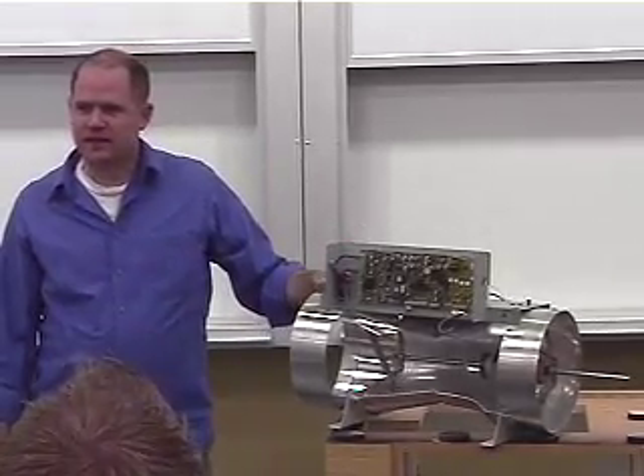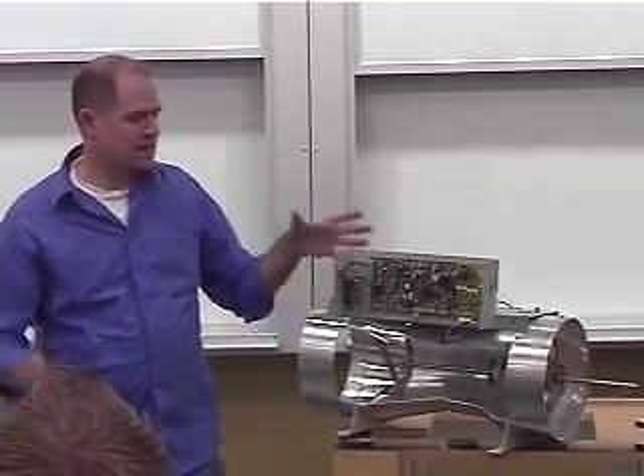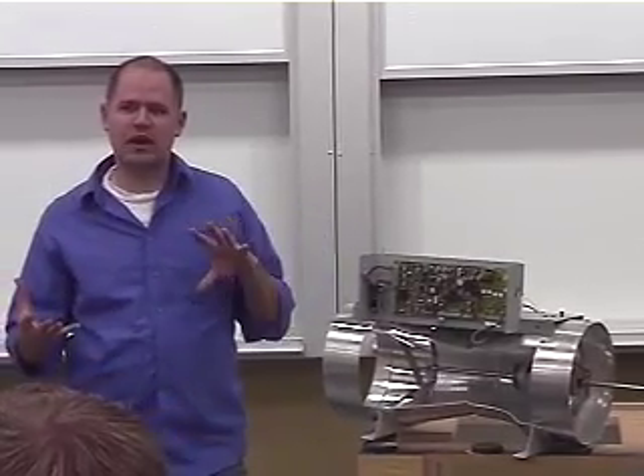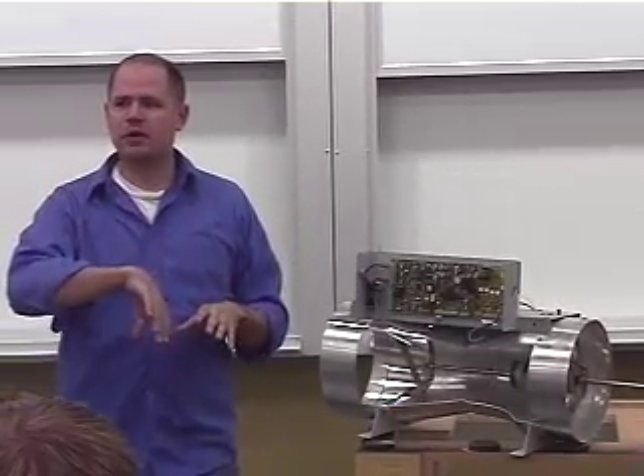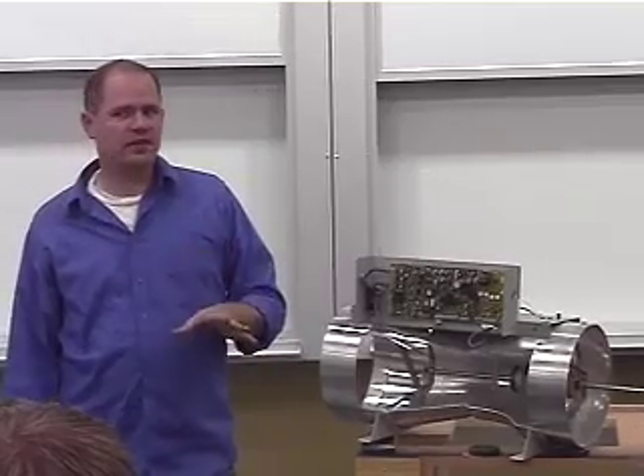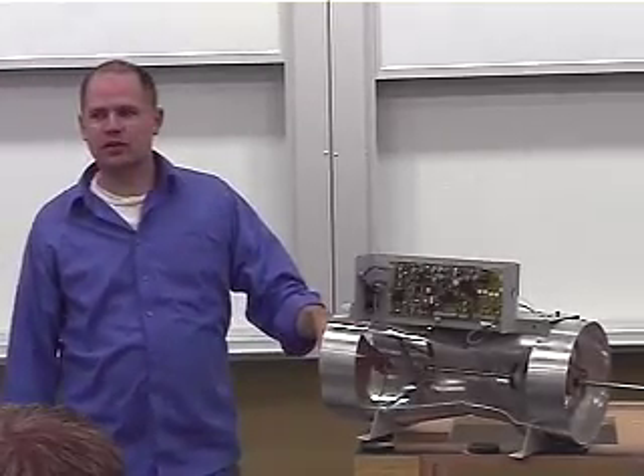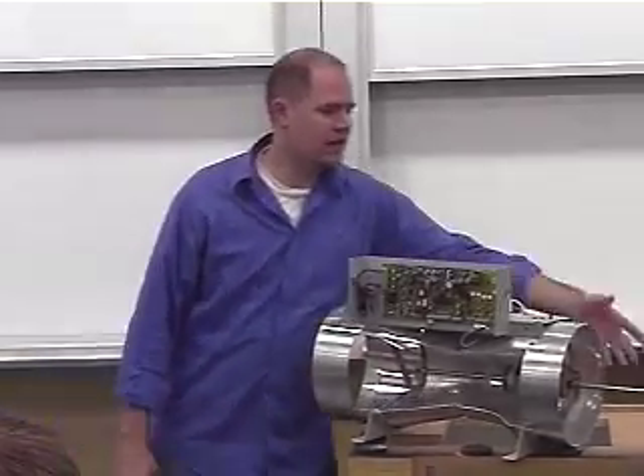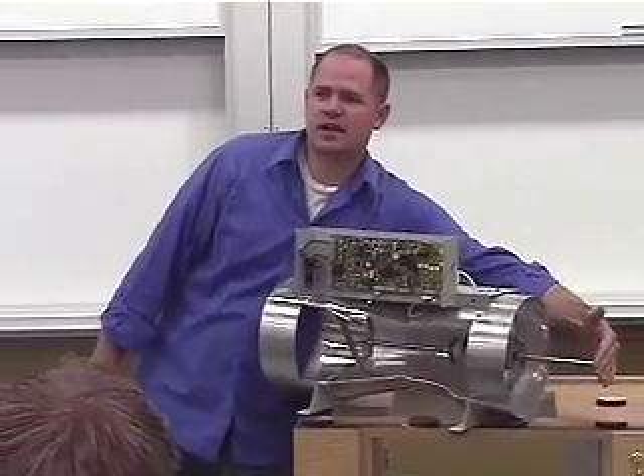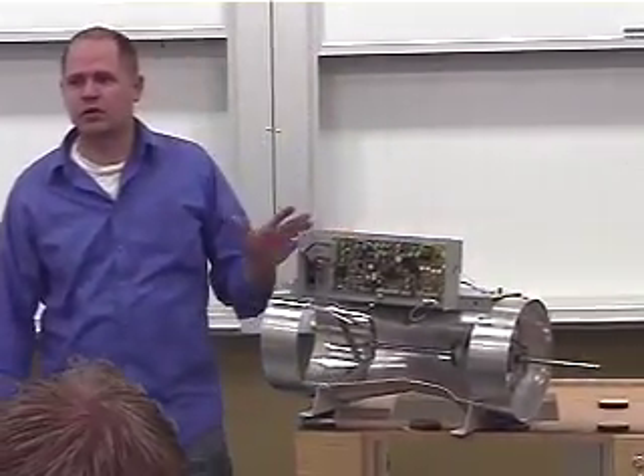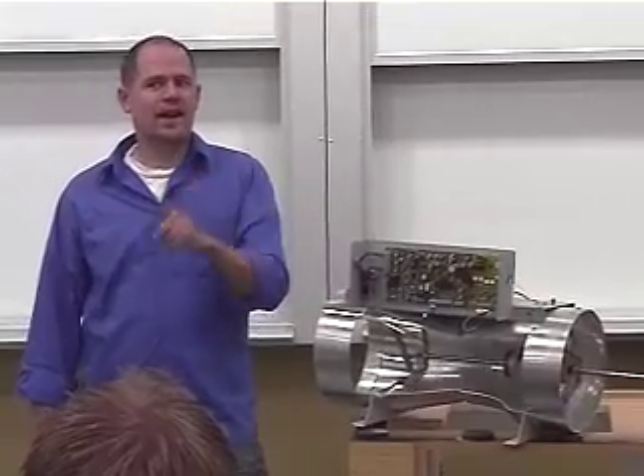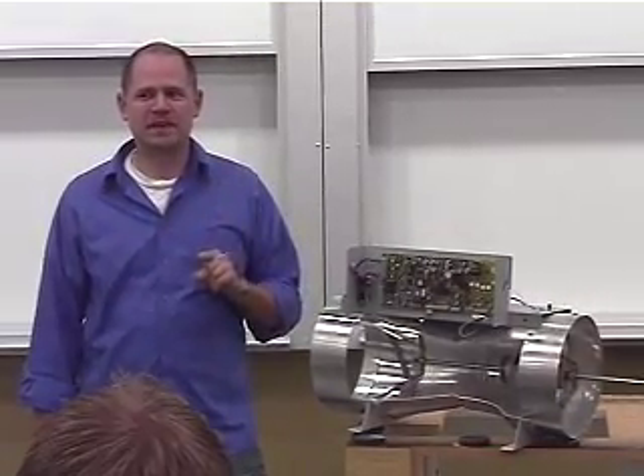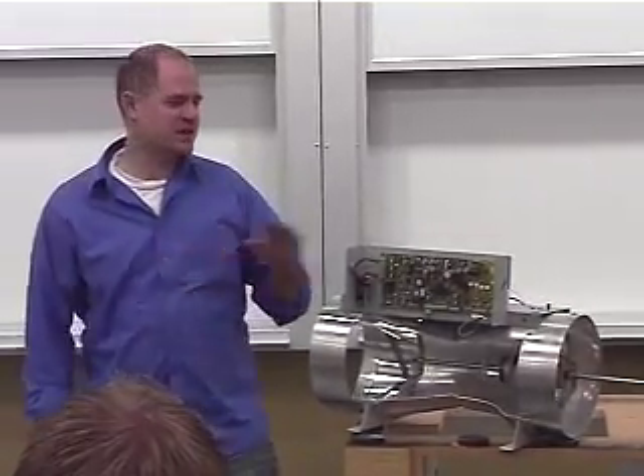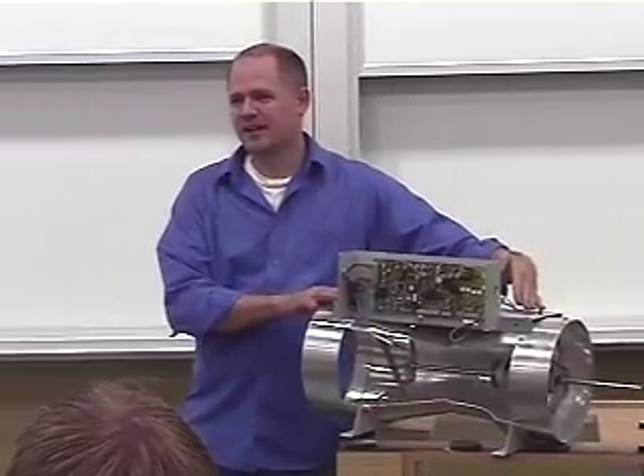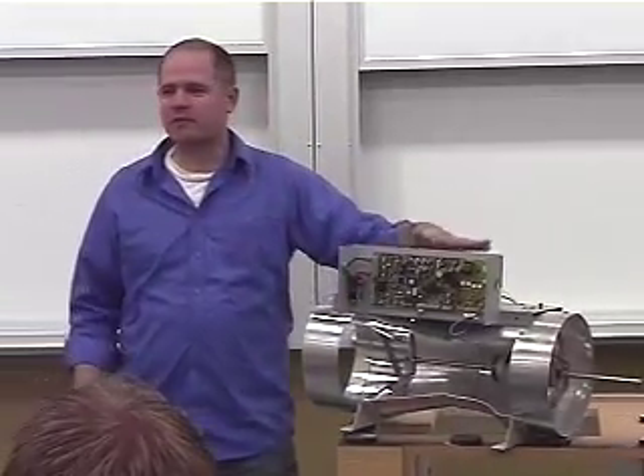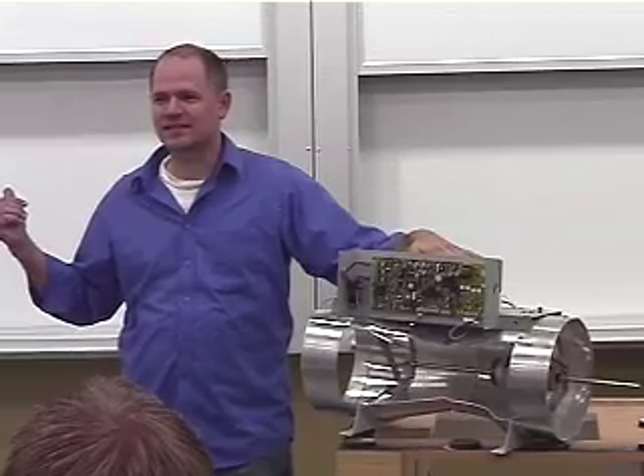One good thing about the Phoenix valves and any Venturi valve design is that if you have airflow that's going around the bend real quick and coming in here, it does not have any problem maintaining the correct values coming through here. You can have a 90 right on the end of this as long as this bar isn't hitting it, and it'll maintain the flow correctly. But that 90 is adding restriction to your system, so you need to be aware of that to make sure that you still have your pressure drop. Putting in as many 90s as you want is not a problem for this, it's a problem for your fans.